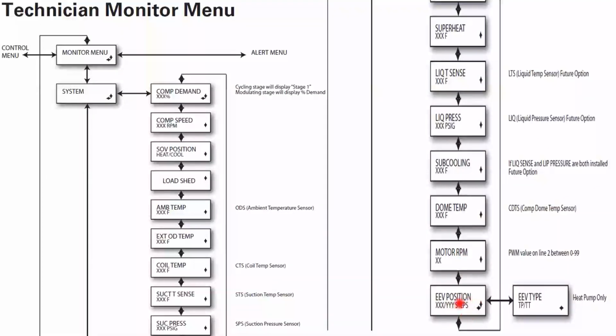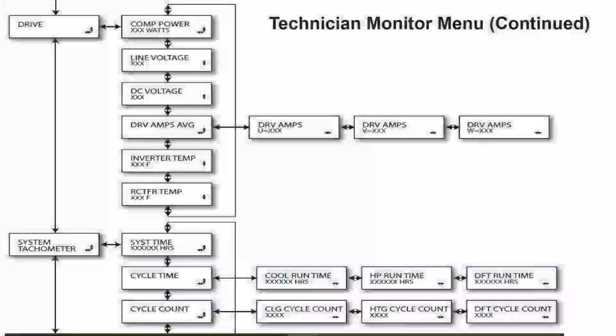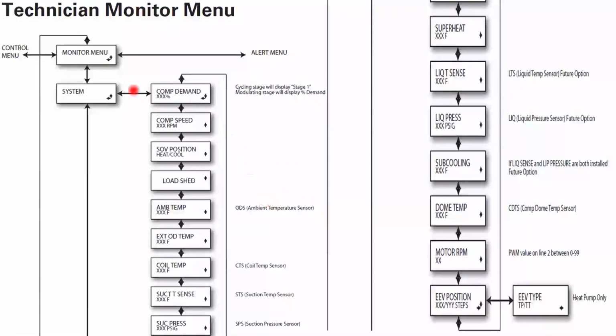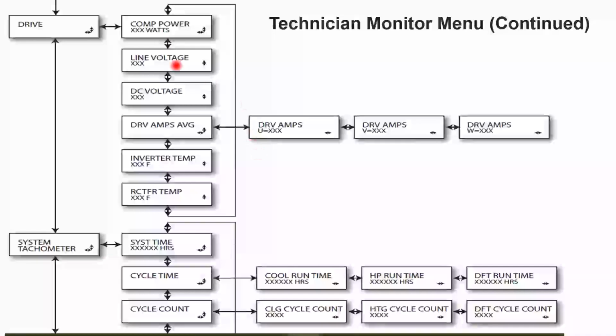Here's our EEV positions. 500 EEV position 500 is all the way open. 0 is all the way closed. Our drive. So monitor menu, we went down 1 and over to the right, and now we see our system. So if we go from monitor menu to system, scroll down 1 more, is our drive.